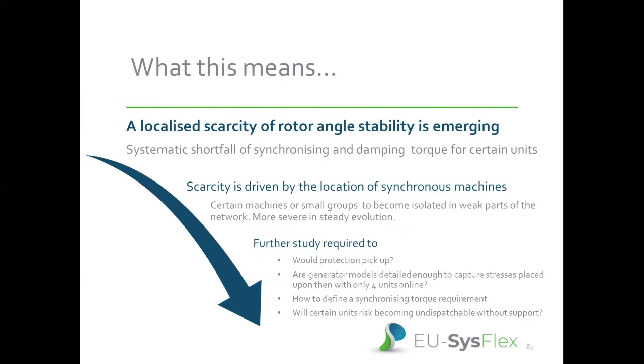As you can see from all the results, we have a localized scarcity of rotor angle stability emerging across all the metrics. There's a systematic shortfall of synchronizing or damping torque for certain units under certain conditions. And again, that's heavily driven by the location of synchronous machines. And going back to that situation where if you have high SNSP, you have a certain amount of synchronous machines on still, and it's really about which units are in that small group. It's not always about the size of the group, it's sometimes about the membership of the group. A single isolated unit can drive a lot of problems.